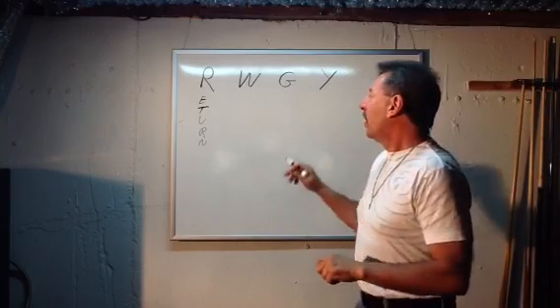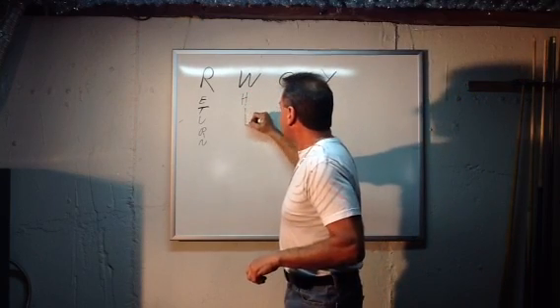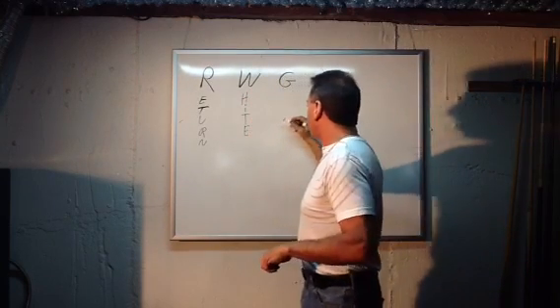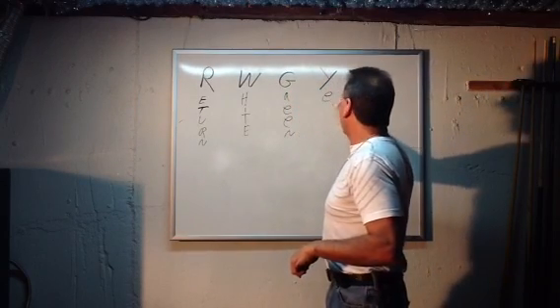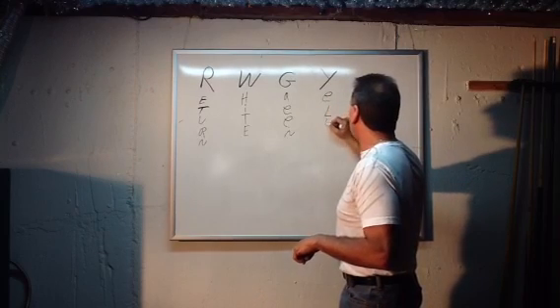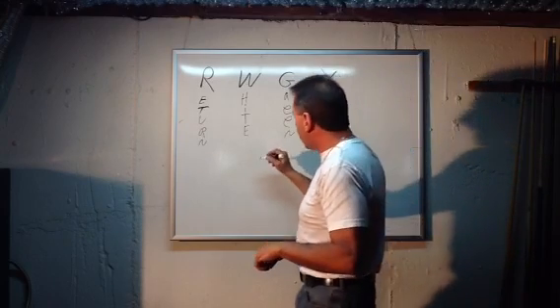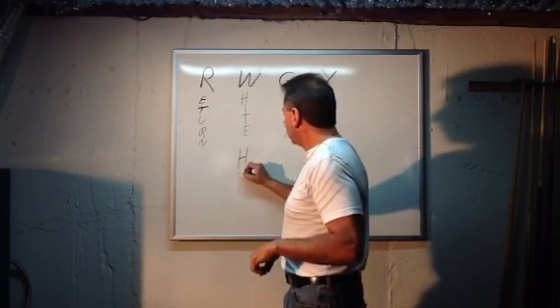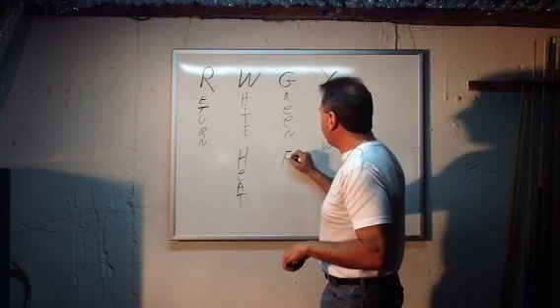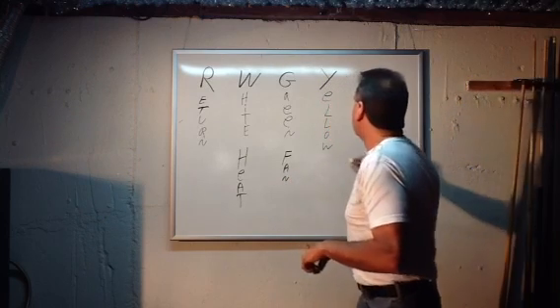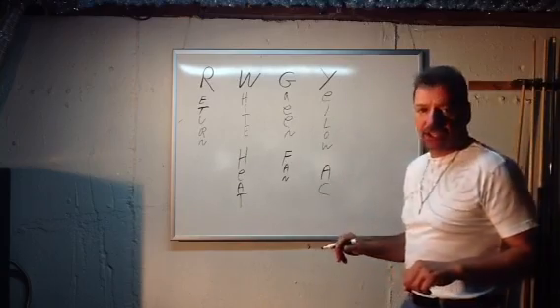The W stands for white, G stands for green, and Y stands for yellow. The white is heat, the green is your system fan, and the yellow is normally your air conditioning, central air conditioning, or AC, if there's an A-coil in a hot air furnace.